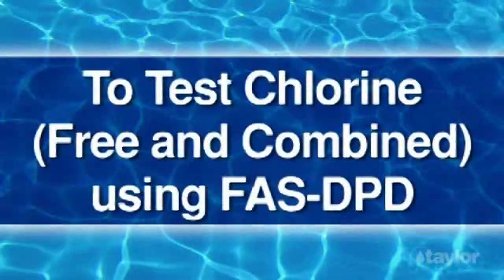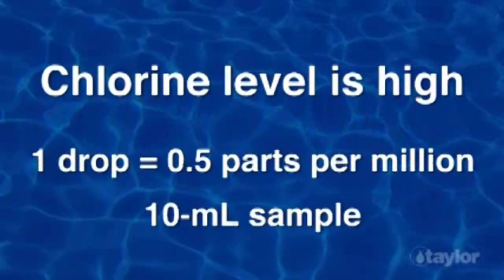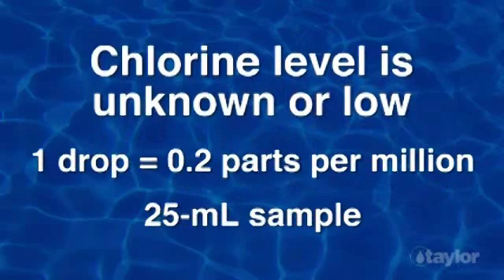To test free and combined chlorine using FAS-DPD, first decide which drop equivalents to use. If you suspect the chlorine level is high — perhaps because the water has been shocked recently — use one drop equal to 0.5 parts per million and a 10 mL sample. This will save time in titrating reagent. If you do not know the chlorine level or you suspect it is low, use one drop equal to 0.2 parts per million and a 25 mL sample.